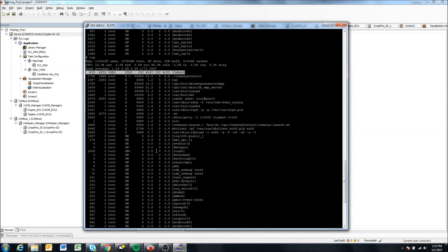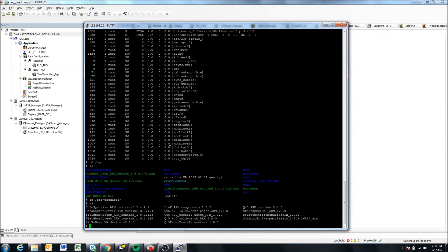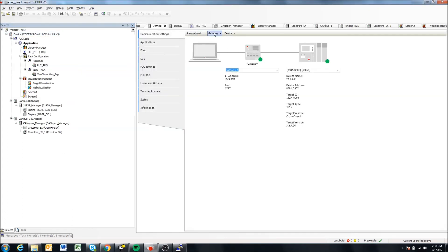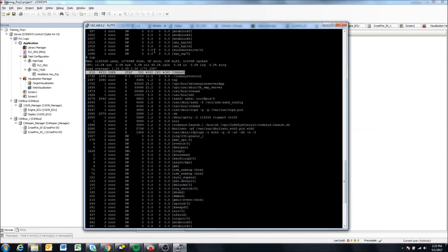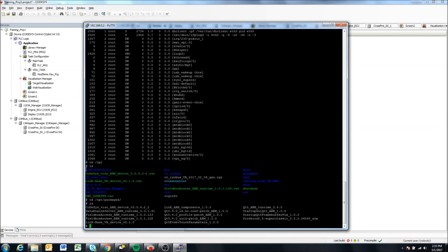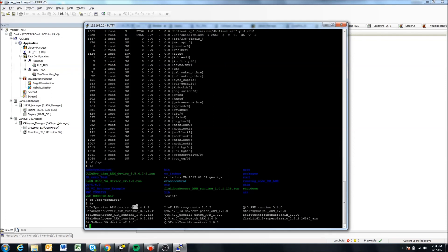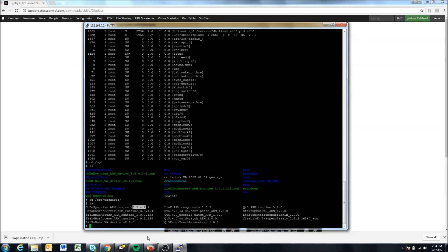I think that covers most of it. In summation, you want to make sure that your gateway settings are correct here. If you're using ARM localhost, if you're using x86, make sure the IP address is located here. Even if you're using ARM, try the IP address if it's not working. Next, check to make sure your runtime is running on the device. So you have this Codesys control process running and your Codesys control folder located in the opt directory of the display will tell you if Codesys is installed. And then lastly, you want to make sure that the device description version and the runtime version on your display match. Hopefully that should help troubleshooting. Of course, if you have issues beyond what I've gone over here, please contact Codesys or Cross Control support and we will help you out. Thank you.